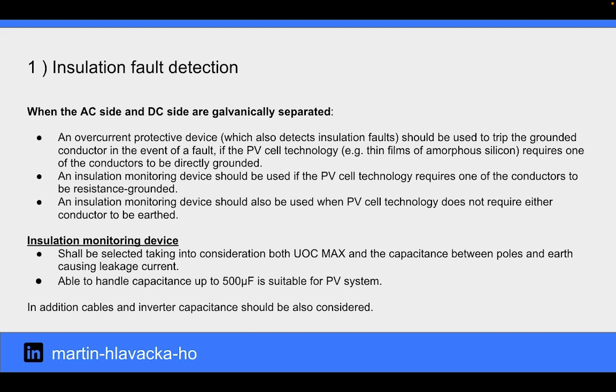Insulation monitoring device shall be selected taking into consideration both the maximum open circuit voltage and the capacitance between poles and earth causing leakage current. In addition, cables and inverter capacitance should also be considered. An insulation monitoring device able to handle capacitance up to 500 microfarad is suitable for PV systems.